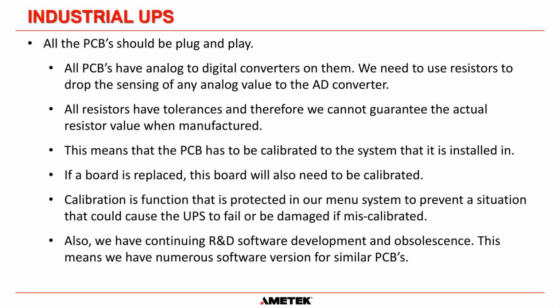So we have to have a way to calibrate each and every individual board for the system that it is installed in. So that means every board can't be plug and play because it has to be calibrated. Okay. And to do that, you have to go through a special engineering password protected menu system, because we can't allow our customers into that menu system. There are so many things that you can change that if you just change one digit accidentally, it could cause your system to blow up and be really in a bad situation. So we always have it so that it's a password protected area where we can go in and calibrate those systems for you.